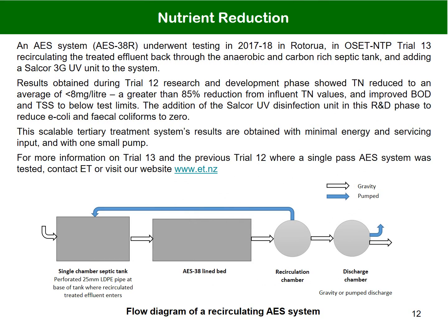An AES system, AES 38R, underwent testing in 2017 and 18 in Rotorua in OSET NTP Trial 13. This involved recirculating the treated effluent back through the anaerobic and carbon-rich septic tank and adding a Salcor 3G UV disinfection unit to the system.